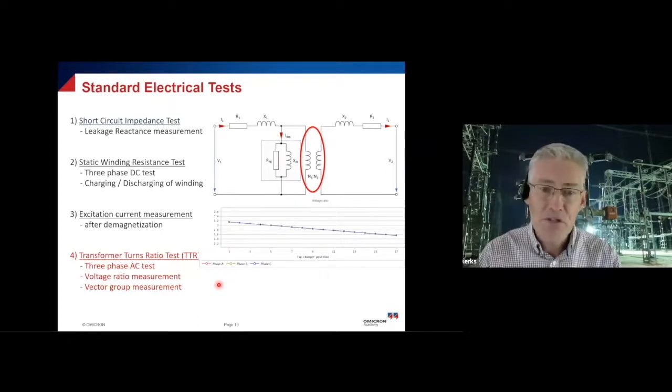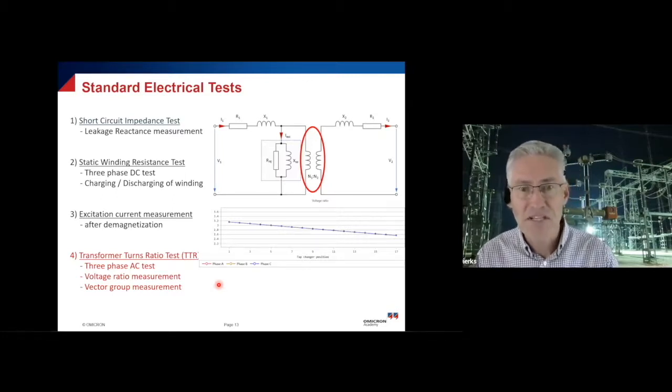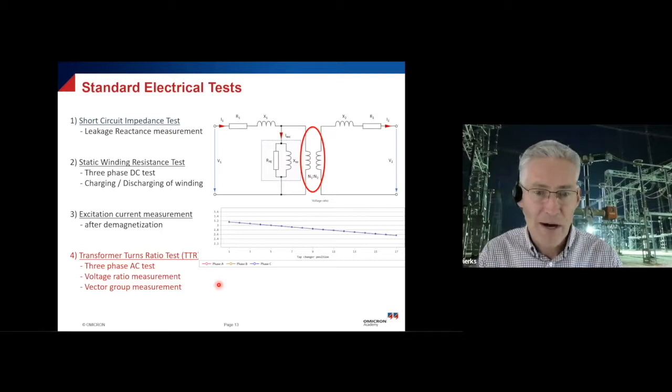And you can plot those also versus the different tap numbers. And again, they should all be on a very straight line from tap number one up to, for instance, tap number 17 in this case. Each phase should be on top of each other because the three windings are again very much identical.